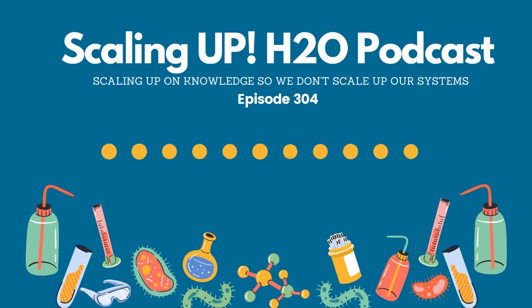After the exposure period is done with the corrosion coupons, that means you put them in the system, you label the envelope, you've taken them out of the system, you finish labeling the envelope, and now you send them off to a lab and somebody like me gets them. Here's what happens when they go into a lab. When we get them, we catalog everything. Whatever you send us, we make sure that we take good notes on, and we note if they are urgent or just regular coupon runs. If they're urgent, it means we're going to put those ahead of everything that we do. If they're just regular coupon runs, then we're going to run those the next time we run all the coupons in our lab.